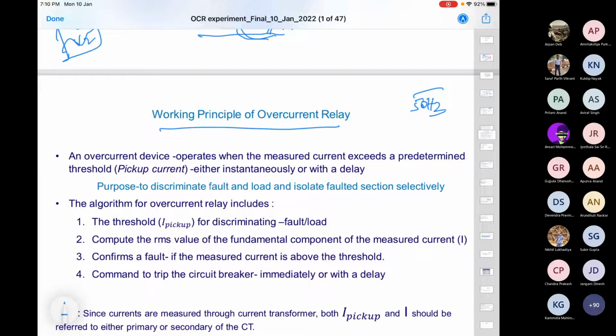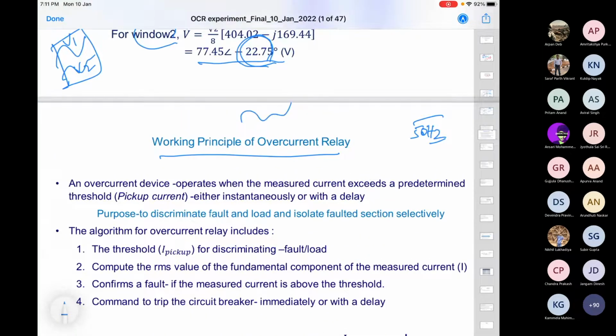And why do we require that? We don't know whether the circuit breaker will open or not. Even if the circuit breaker will open, can you say that correctly or not? How much time will it take? All are uncertain. And because the relay has the capability to store the data, the window will go on moving forward. For the decision, the relay will go on continuously. For this corresponding fault signal also, the window will go on moving and moving forward till the current becomes zero in that path.